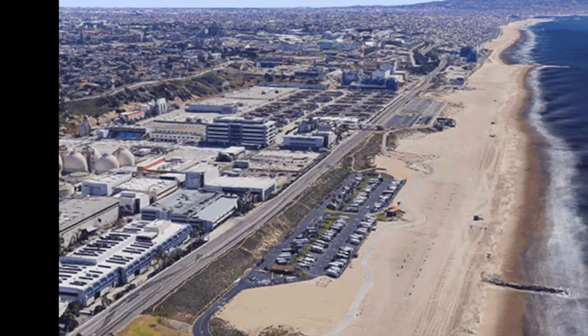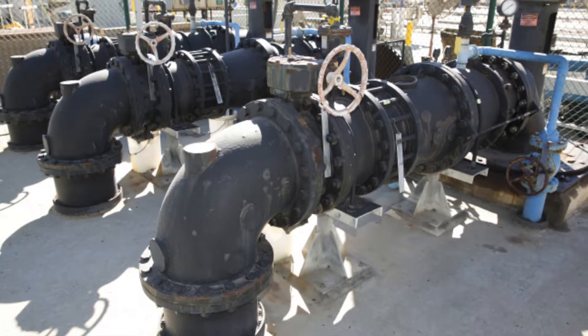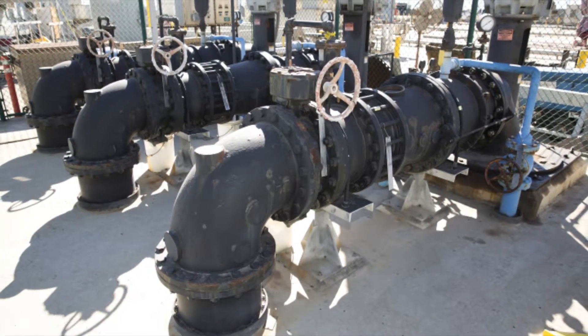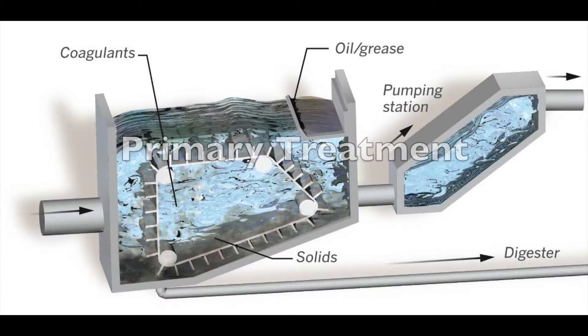With the use of many technologies, the rigorous treatment process begins with sewer lines that bring in about 350 million gallons into the plant, where it is screened for larger objects at the headworks. The water is then brought to tanks where larger objects settle to the bottom, and the liquid is pumped with large screw pumps to the secondary treatment system.